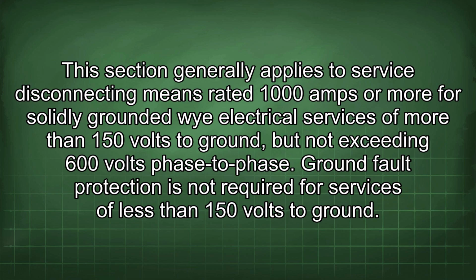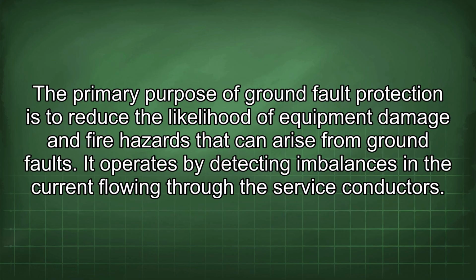This section generally applies to service disconnecting means rated 1000 amps or more for solidly grounded wye electrical services of more than 150 volts to ground, but not exceeding 600 volts phase to phase. Ground fault protection is not required for services of less than 150 volts to ground. The primary purpose of ground fault protection is to reduce the likelihood of equipment damage and fire hazards that can arise from ground faults. It operates by detecting imbalances in the current flowing through the service conductors.